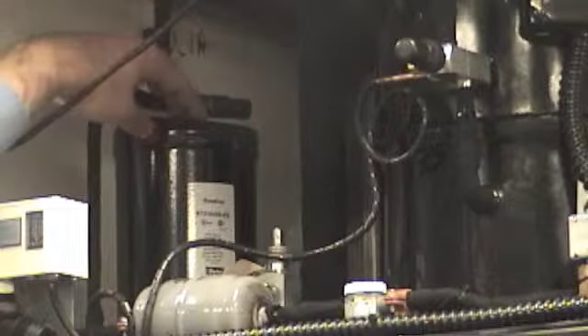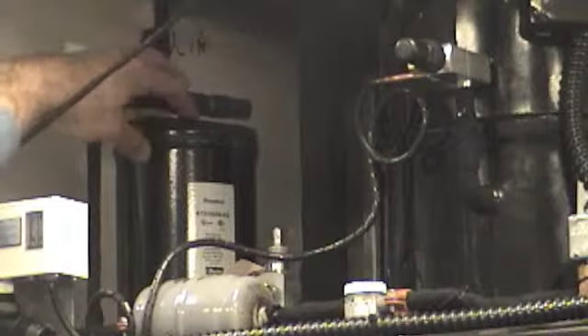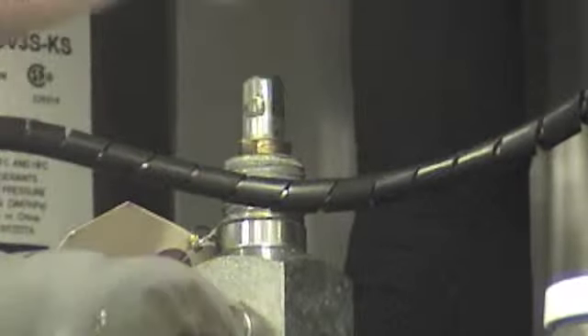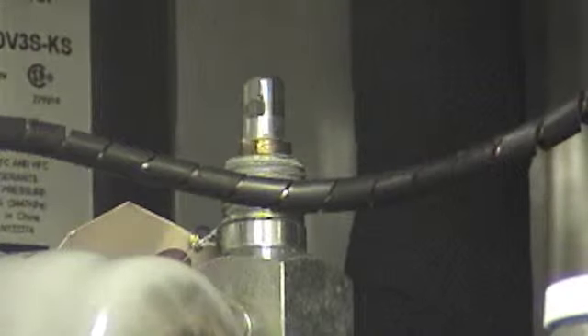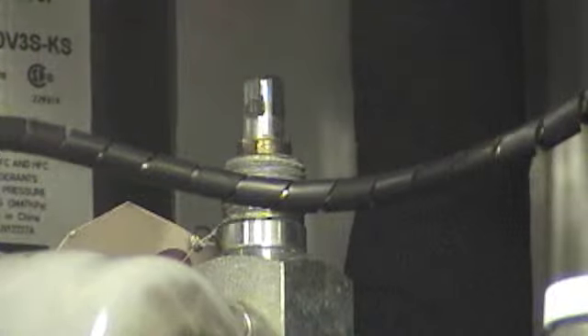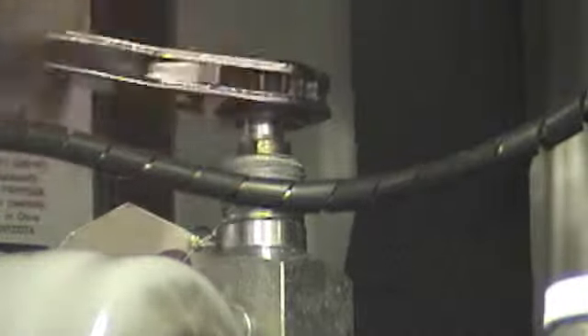Now we're going to go ahead and start to open up the refrigeration system. On this unit, there are 3 valves, one on the top of the receiver. All the refrigerant is pumped down into the receiver for shipment, and then on the high and the low side of the compressor. So for a valve with a packing like this one, this valve doesn't have a packing obviously, but the valve on the top of the receiver does, and this one does. You want to be sure to loosen that packing slightly before adjusting the valve, opening the valve. So once it's adjusted, you can make sure you can open it up.